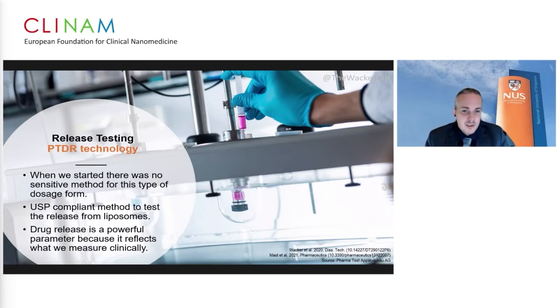And when I started with this research around 2010, there were not actually a lot of methods to measure the drug release. There was one commercial product, and that was, sorry to say, poorly standardized. So what we did is we built our own equipment, and now you can see this dispersion releaser cell, a USP apparatus with a release cell based on dialysis, from which this pink liposome releases its compound. We built this cell into a USP, United States Pharmacopoeia dissolution tester, in order to also follow international standards.